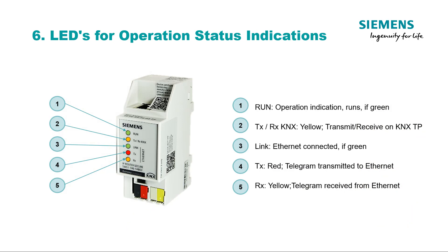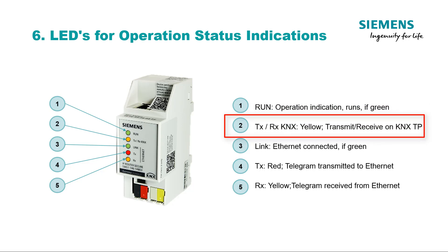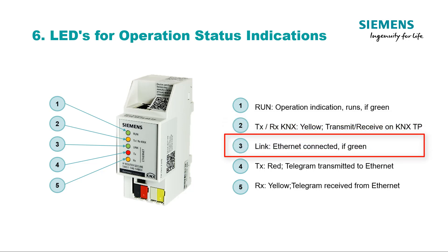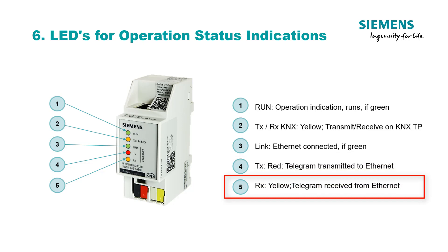LEDs for operation status indications. Five LEDs inform about the operating status of the products. The Run indicator lights green when the products are ready for operation. TX-RX-KNX lights yellow when KNX telegrams are sent or received on the twisted pair side. The Link LED lights green when the Ethernet connection is active. TX lights red when telegrams are being sent on Ethernet. RX lights yellow to indicate receipt of Ethernet telegrams.